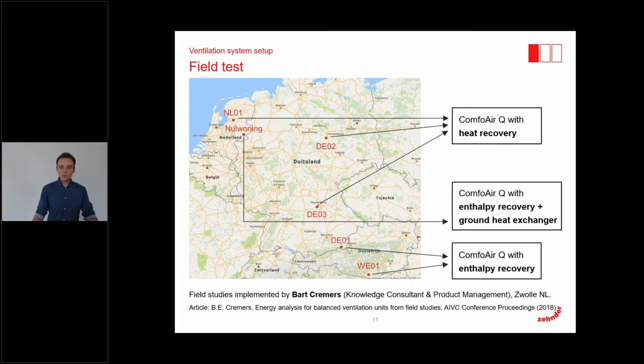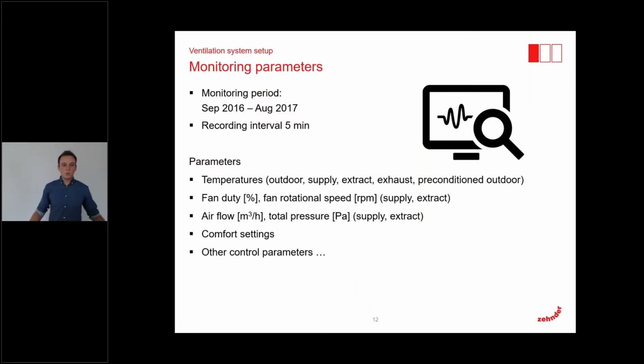So we have 3 ComfoAir Q units with heat recovery, 2 units with enthalpy recovery, and 1 unit with enthalpy recovery and additionally the ground heat exchanger. These units were located in the Netherlands, in Germany, and in Austria. The monitoring period started in September 2016 and ended in August 2017. So we built up a whole year. The recording interval was 5 minutes, and he measured the temperatures and humidity of all air streams, the fan duty, the rotational speed of the fans, the airflow rates, and the total pressure.